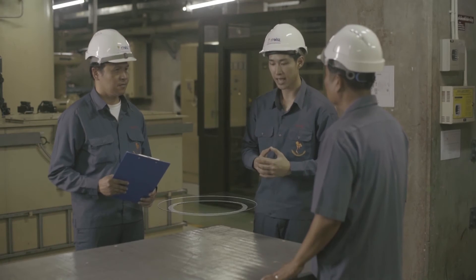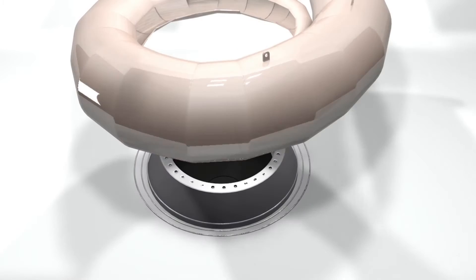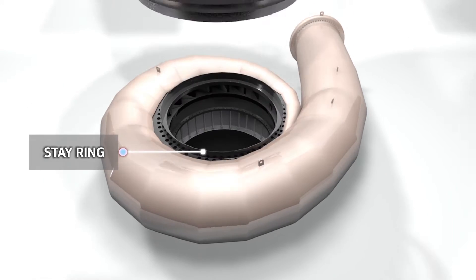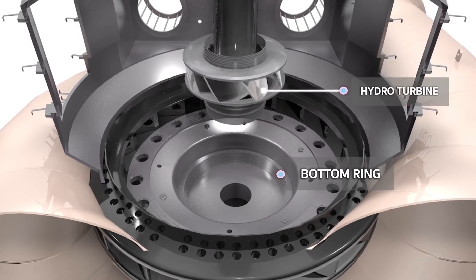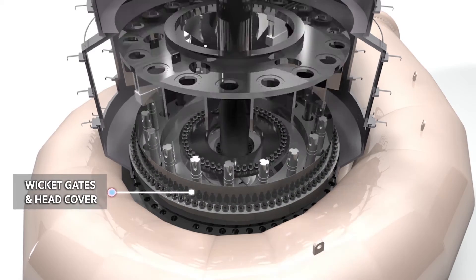This is how the mechanical equipment is being installed. Starting from installing the platform equipment, then overlaying the platform with concrete. After that, install the spiral case, then install the draft tube for controlling the water flow to downstream. Then install another platform for the hydro turbine, encase the spiral case with concrete, and install the hydro turbine connected with the shaft. Finally, install the water flow control system for the hydro turbine.